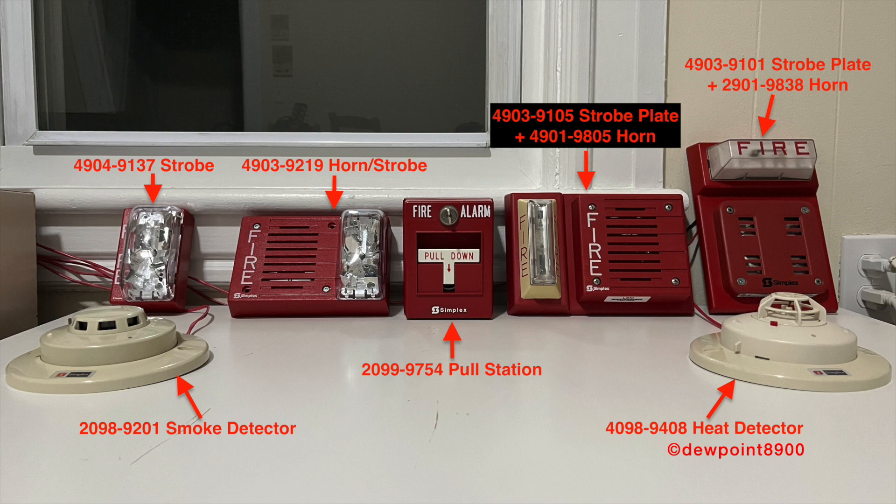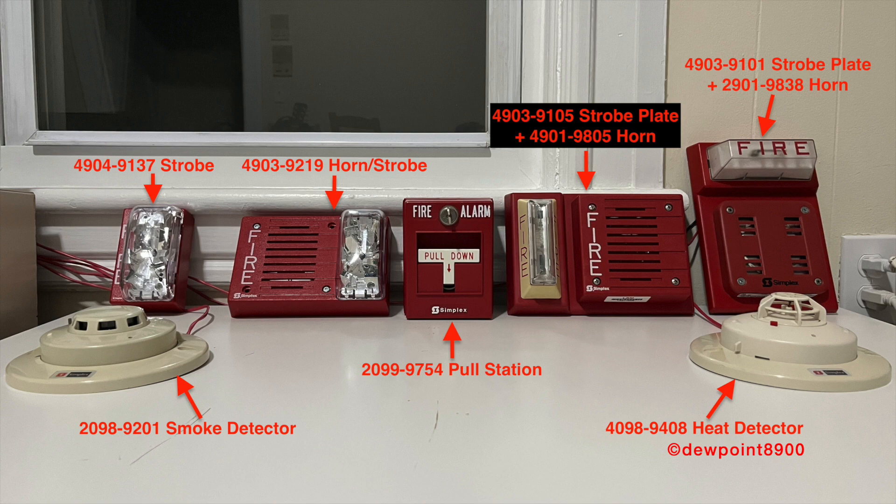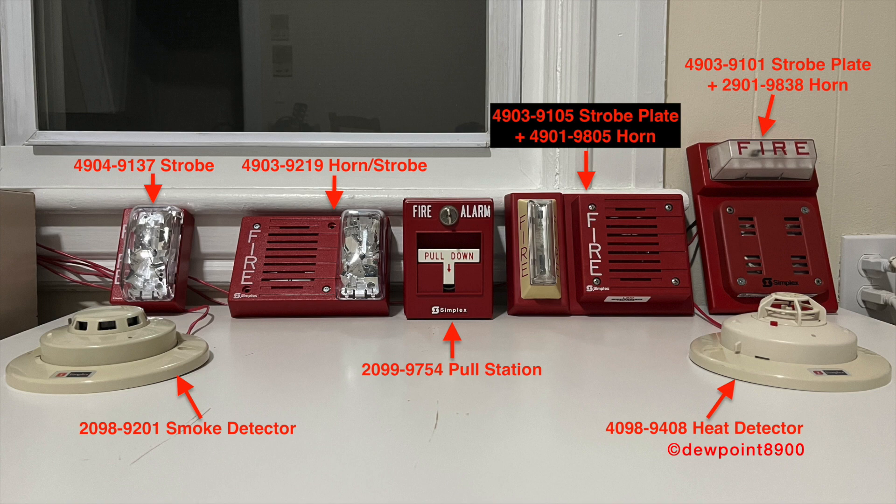The 4005 is programmed for selective signaling by zone. Each initiating device is connected to its own zone on the panel. When the smoke detector activates, the signals to the left of the pull station will sound in temporal coding. When the heat detector activates, the signals to the right of the pole will sound in march time. There's also a 2098-9806 remote test station near the panel to demonstrate the supervisory condition.